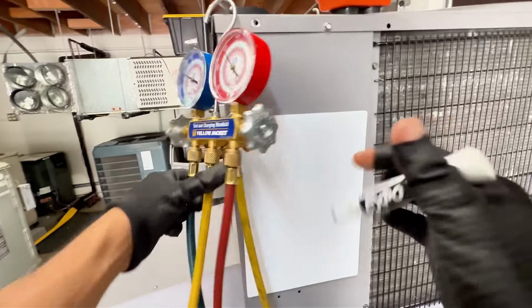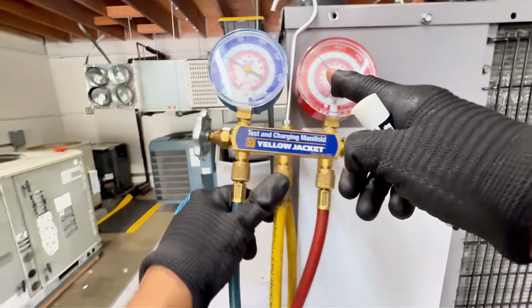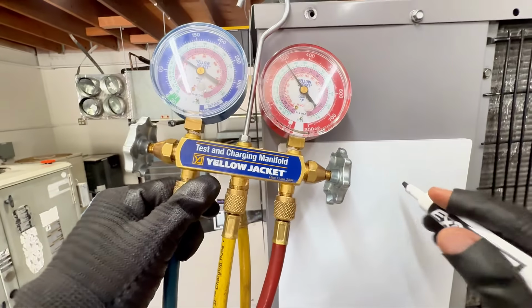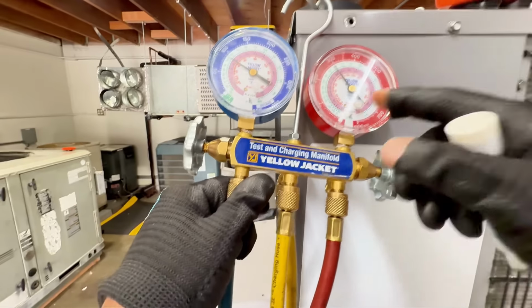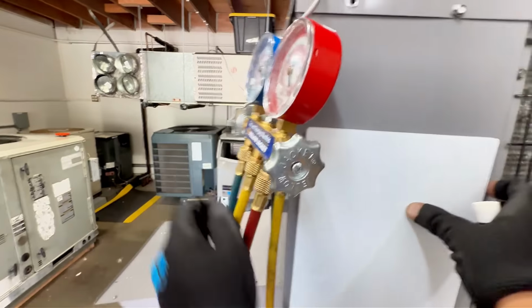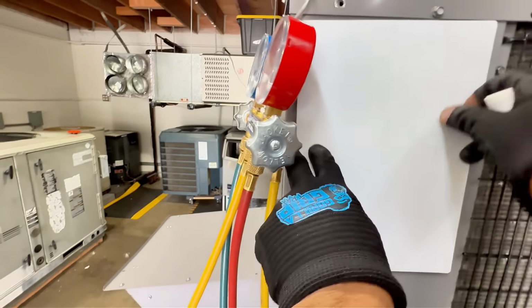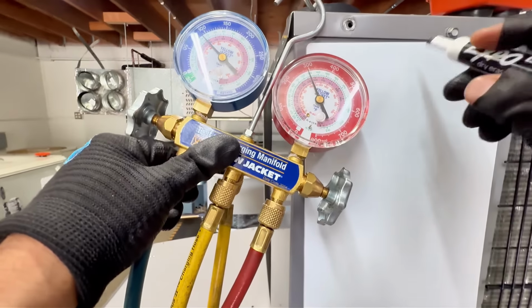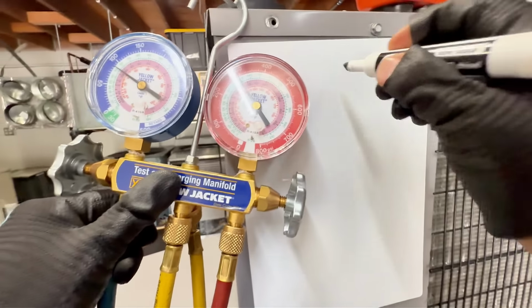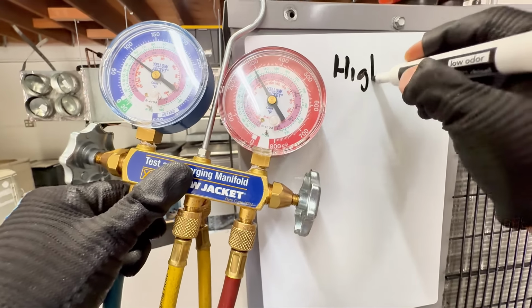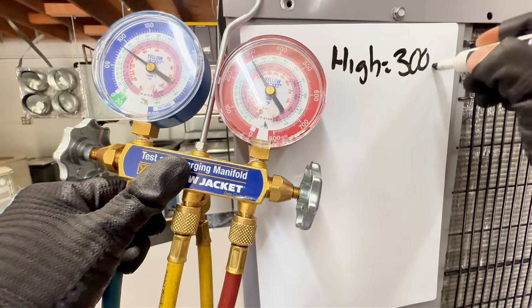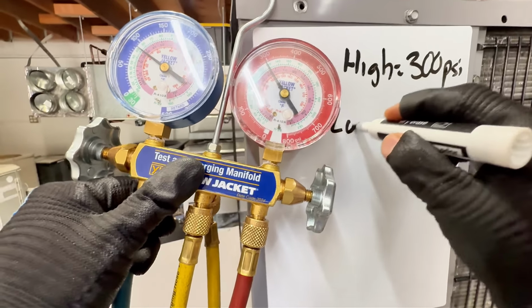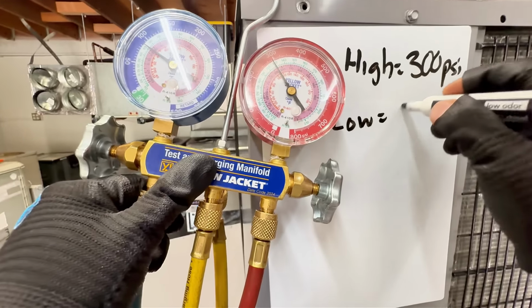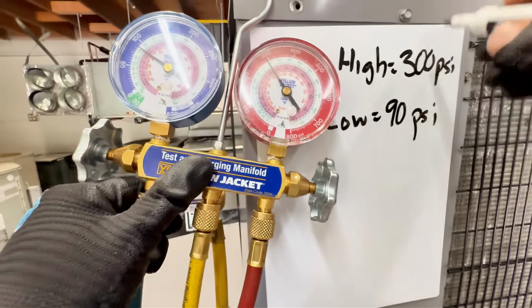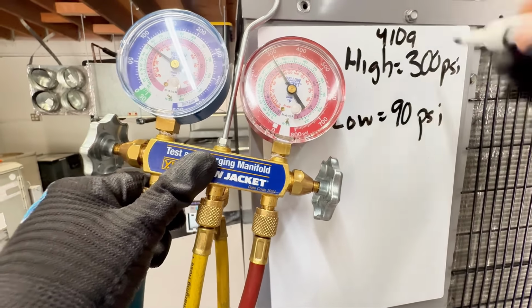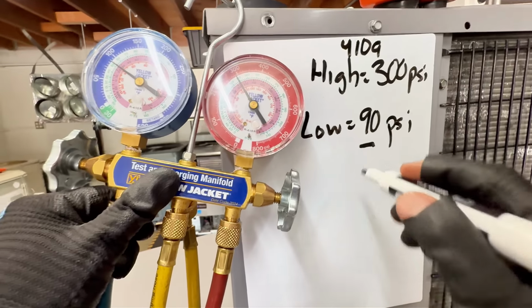So let's go ahead and get numbers. I know I should have waited a little bit more, but I don't want to keep you guys waiting too much. And honestly, I'll be able to find out if we have an issue or not by looking at the numbers, and I'll explain them right now too. For my high side, I'll put high, it's 300 PSI. For my low, it's 90 PSI. Right away, remember, this is a 410A system. Right away, that tells me something.